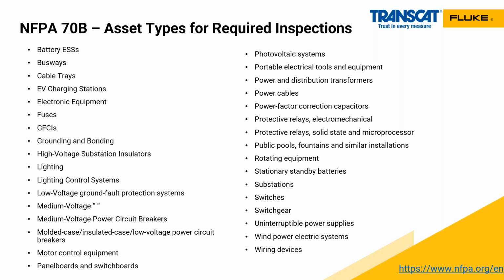So, low voltage ground fault protection systems. What's considered low voltage? Well, believe it or not, 1,000 volts or below is low voltage. I know you might think 480 is high voltage. It's not. Medium voltage is everything above that. Do you have lighting circuits? Are they 120 or 208? Yes, that would be the case. Do we have battery systems? Those are what, 12 volt, 24, 48 volts? Yes, DC again. Fuses, GFCIs. Yeah, we could go pretty low with this, can't we? If you think about it, I'd say at least down to 120 volts AC, and then certainly all the way down to probably as low as 12 volts DC, if it's a fixed battery system. It's all in the works here, frankly.